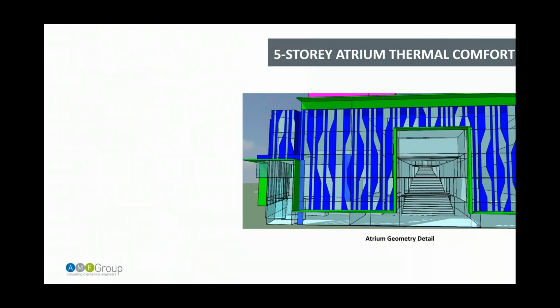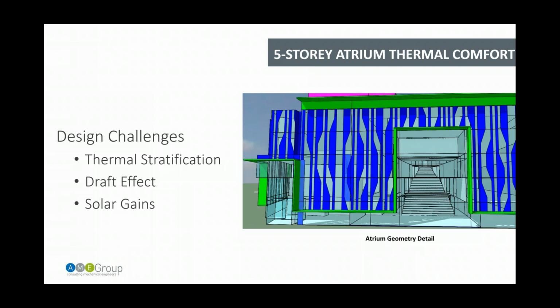The next issue that we saw was the 5-story atrium and the thermal comfort issues that we knew we were going to have. We're not as cold here or as hot as in the Lower Mainland, but we still have this big atrium, and you can see the glazing on the bottom left and the center of the building there, that's all facing east. So we knew we'd have big solar gains, and some issues in the winter with a lot of the chill coming down the windows. We wanted to model this to avoid any discomfort for the students, because that atrium was going to be used for gathering spaces for not just the university, but possibly rented out to other people for different events. So thermal stratification, draft effects, and solar gains were what we were looking at.